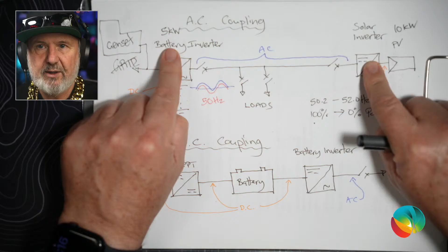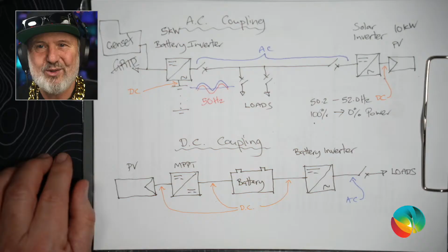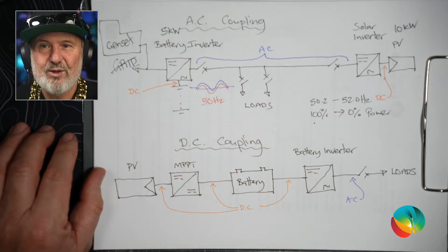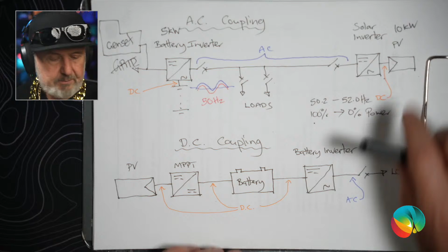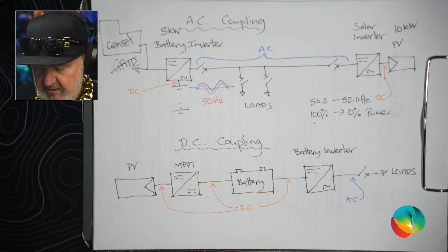solar inverter. That's when you haven't got a grid to spill the surplus to. If you have the grid, you can spill that extra to the grid, but if you've got a generating set, you can't spill anything. You've just got to curtail generation. But there is another way to control the solar inverter, and that's using comms. Now, typically that'll be a wired comms. Most of the systems I've seen use RS485 over a data cable.